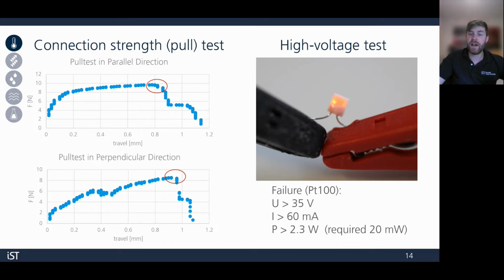On the right side, we have a high voltage test. Pictured here, we have the 100 ohm element. You can see we're really heating it up and it's glowing bright. We're trying to push it to failure. This sensor was able to withstand over 35 volts, over 60 milliamps, and over 2.3 watts. We note here that according to the detail spec, the sensor is only required to withstand 20 milliwatts.